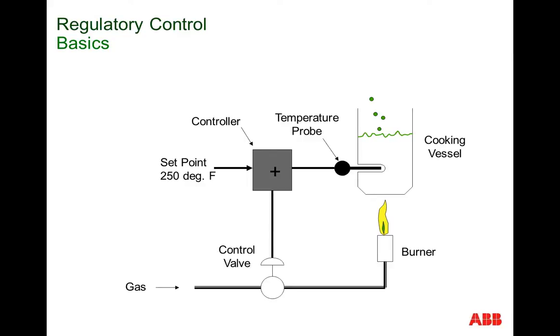Here's a typical regulatory control example. Here we're cooking a batch of soup or chemicals and need to regulate the temperature. Observation is done by a temperature probe that connects to what we call a summing junction, which compares the actual temperature to our desired temperature, or set point. If there's a difference, it opens a gas valve to raise that temperature. Here again, in more or less a closed-loop fashion, we see observation, decision, and effort.